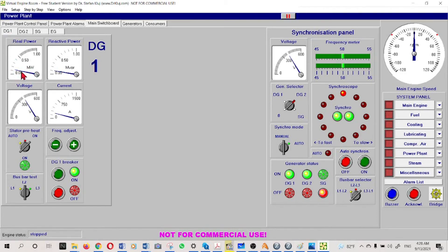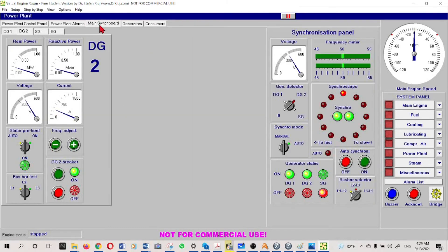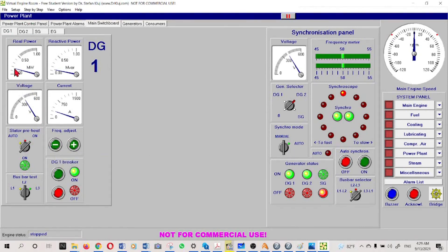Now it starts taking a small load. Diesel generator number one also - the bus bar has a very small load. I will add more consumers - non-essential consumers - and try to increase the load. It is increasing. When I increase the speed, the load increases here.